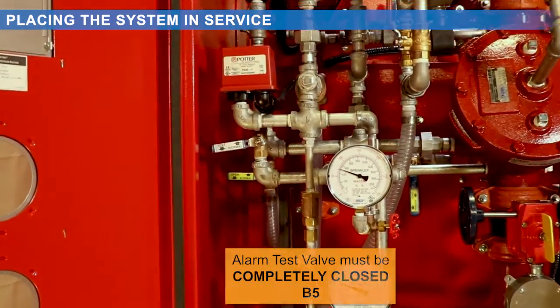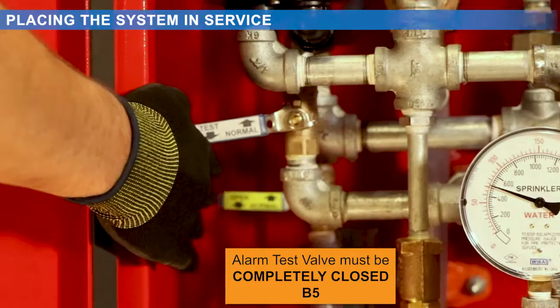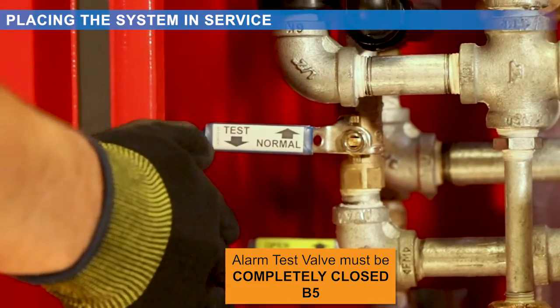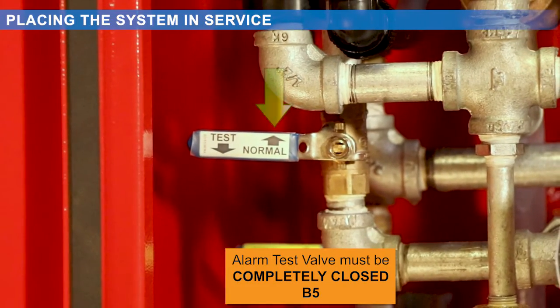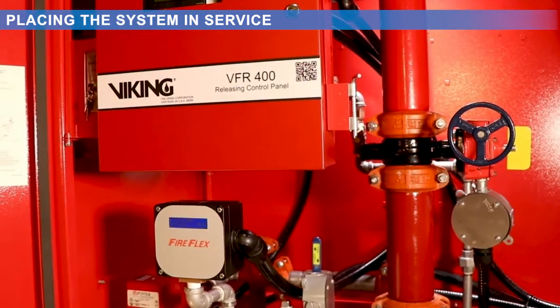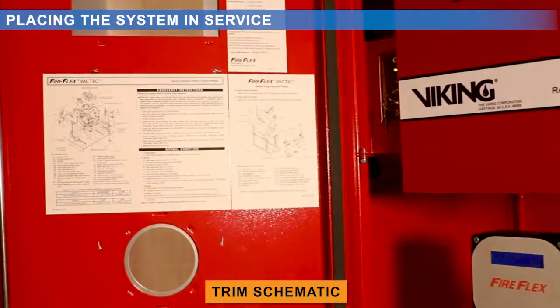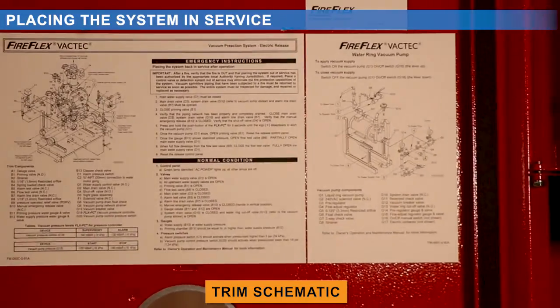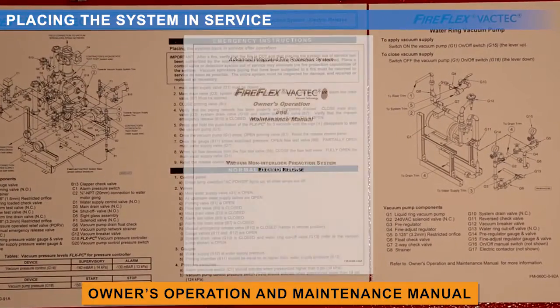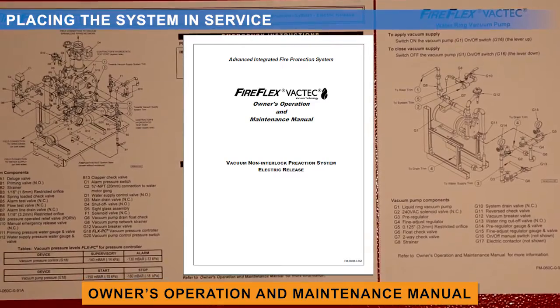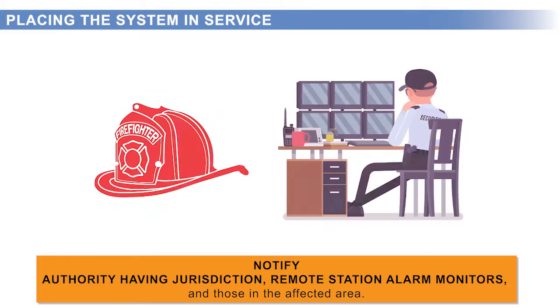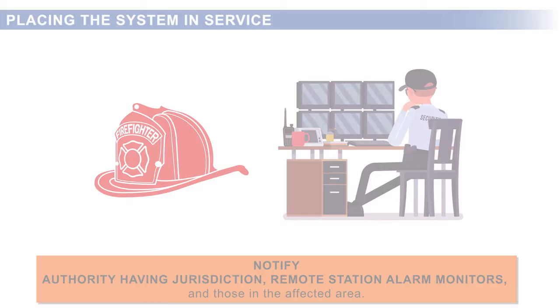Verify that the alarm test valve is completely closed and that all other valves are in their normal operating position. Refer to the adhesive labels on the valve handle. You can also refer to the trim schematic figure on the adhesive labels inside the main door of the Vactec unit or in the owner's operation and maintenance manual. Notify the authority having jurisdiction, remote station alarm monitors, and those in the affected area that the system is in service.